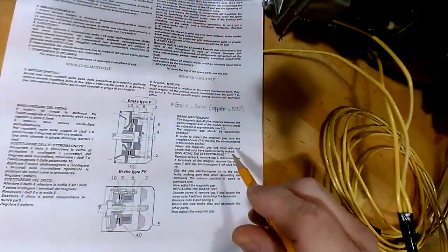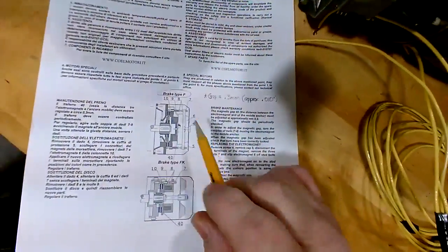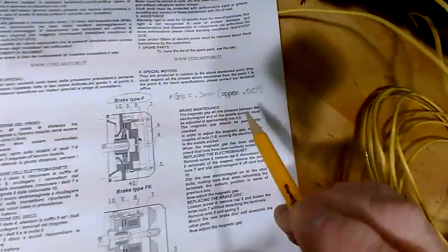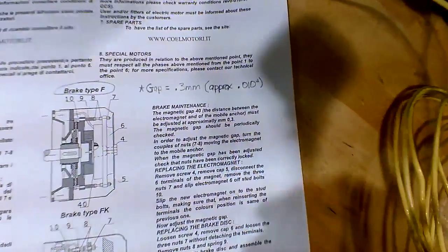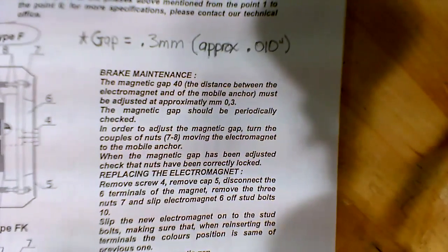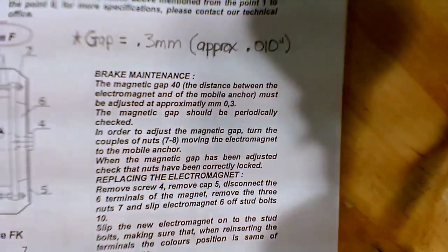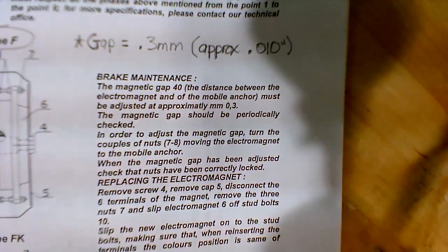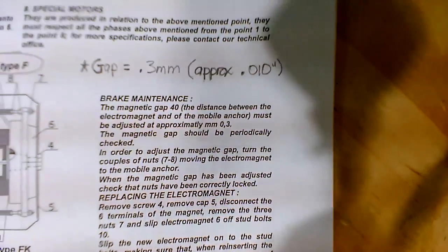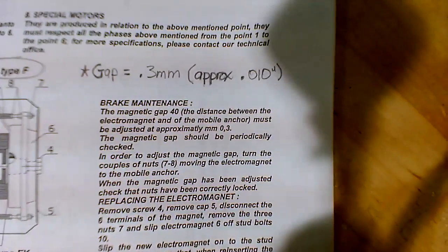Where that comes from is in the procedure here for the brake motor. It's a type F, and the specification says that the magnetic gap distance must be adjusted to approximately 0.3 millimeters, which would be about 10 thousandths of an inch in standard.